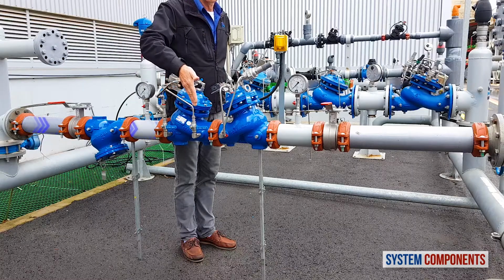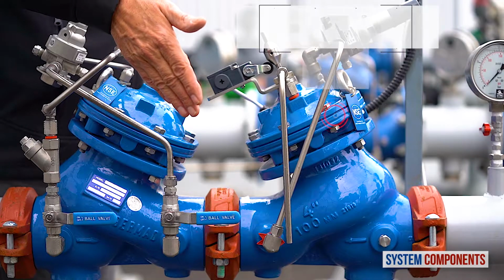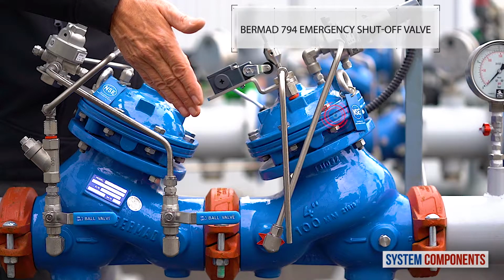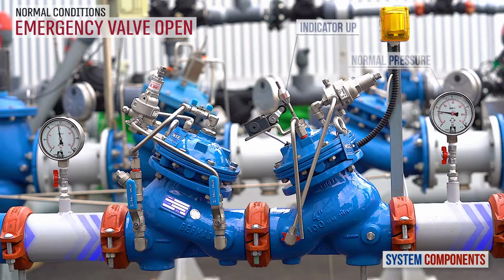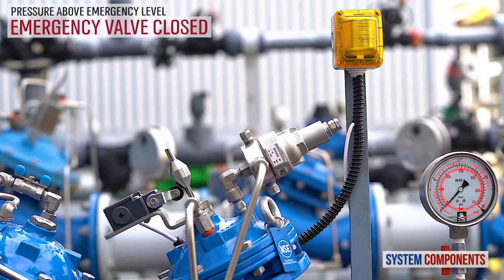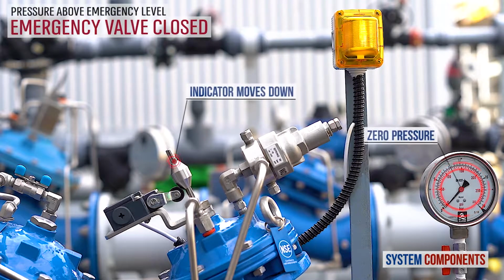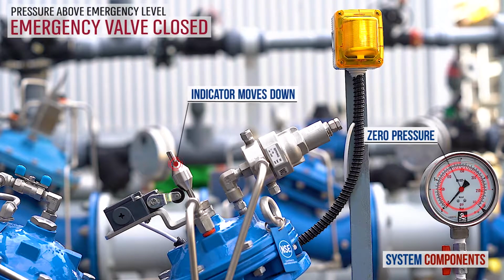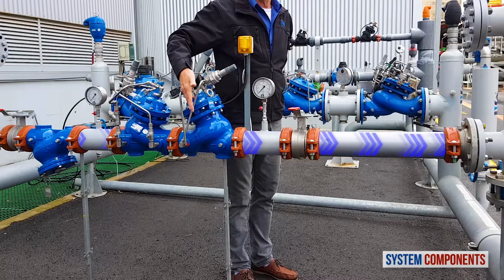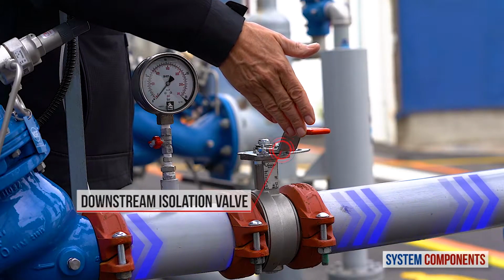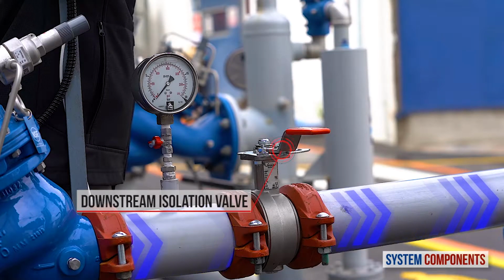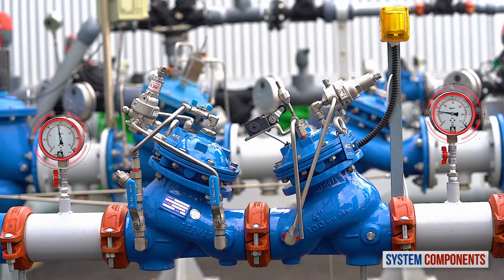The water then passes through the BERMAD 794 pilot-operated emergency shut-off valve. As explained earlier, under normal conditions, this valve is fully open, only entering shut-off when the consumer supply line pressure rises above its preset allowable pressure, which can be adjusted using the pilot. From here, if the downstream isolation valve is opened, the water will go on to the consumer line. Also, in this installation, we have two pressure gauges, upstream and downstream of the emergency and primary valves.